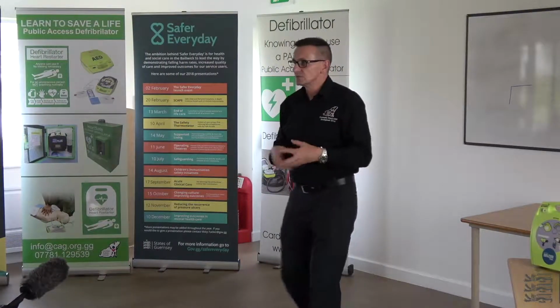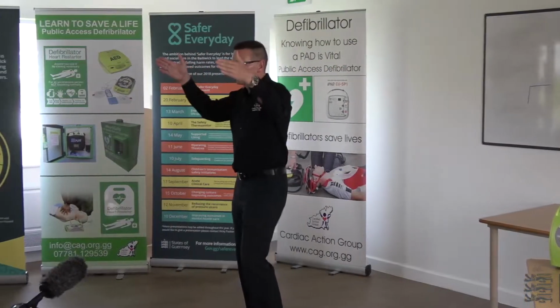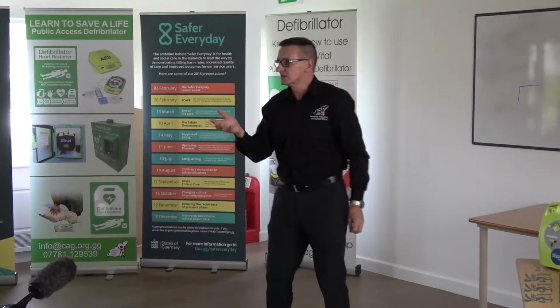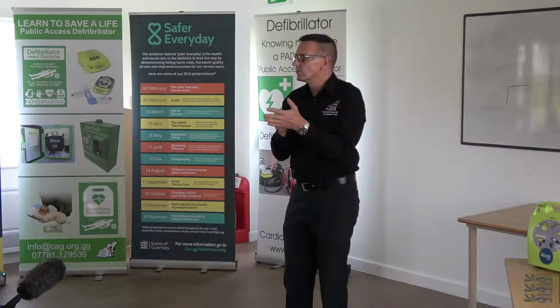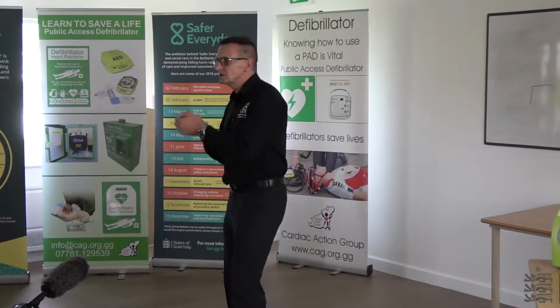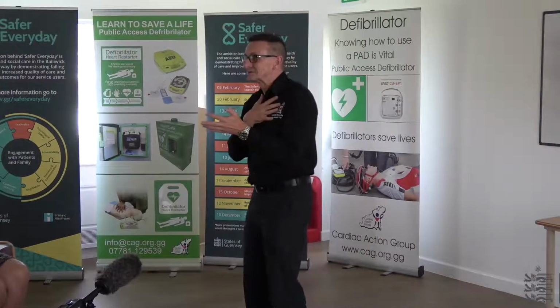When I went down to speak to the chap about doing some training, I said, let's go and have a look at all your defibrillators. Each building is locked, by the way. The doors are locked between each building. So when I walked in, the table tennis centre one had one month to go before it would not have worked. I said to the chap, who's checking your defibrillator? Checking it? They don't check it. Oh my goodness, I was a bit worried about that.